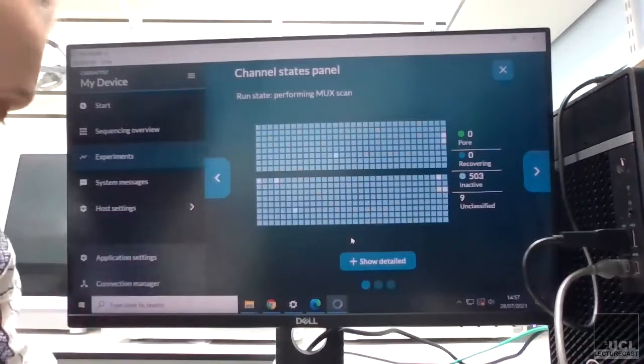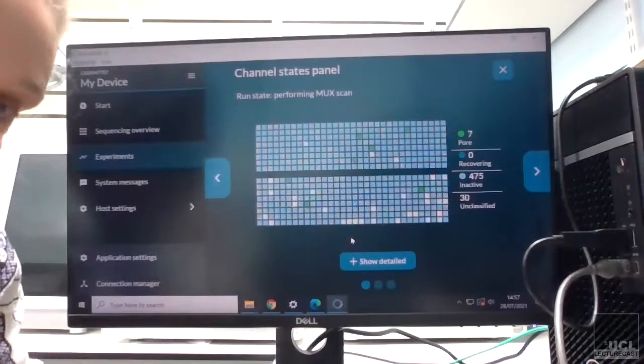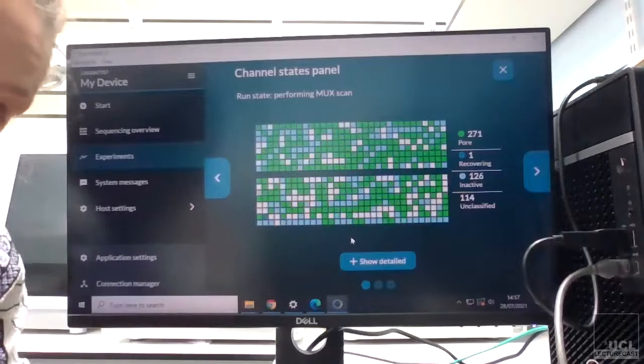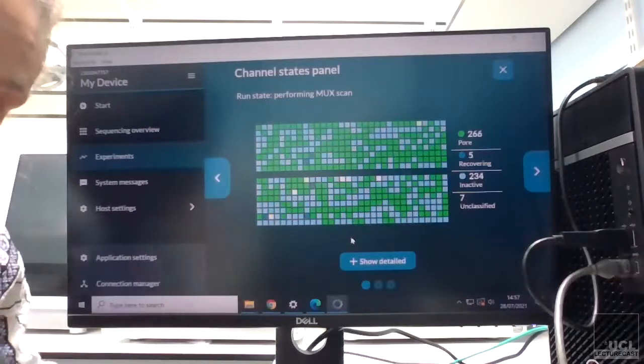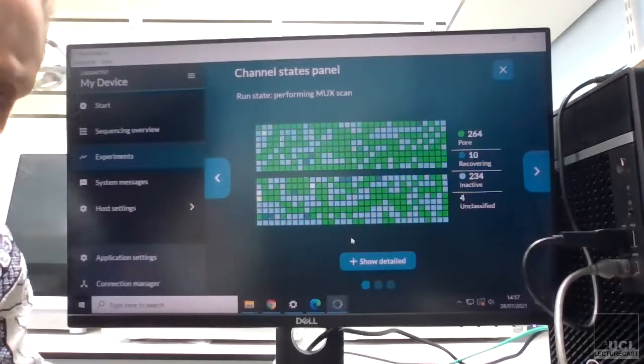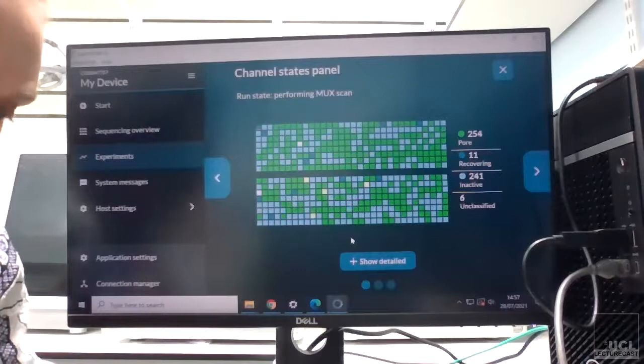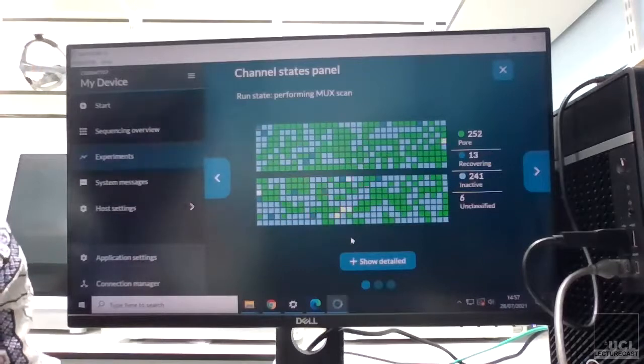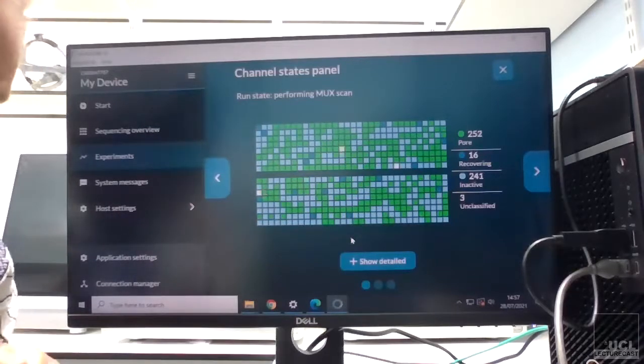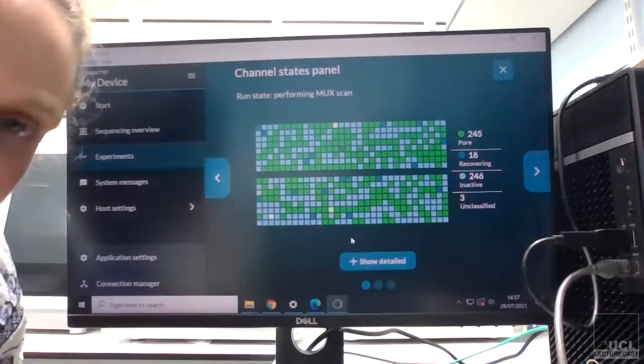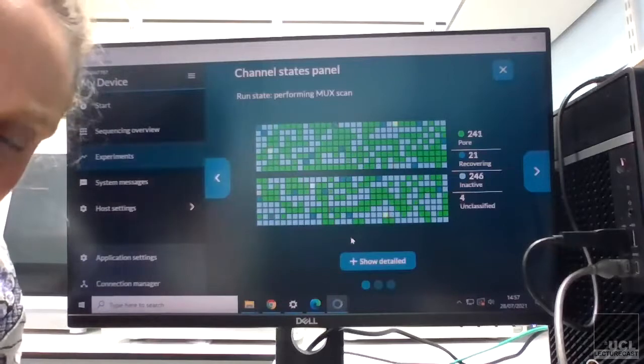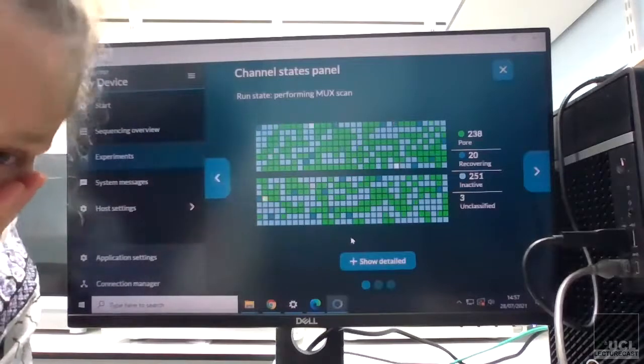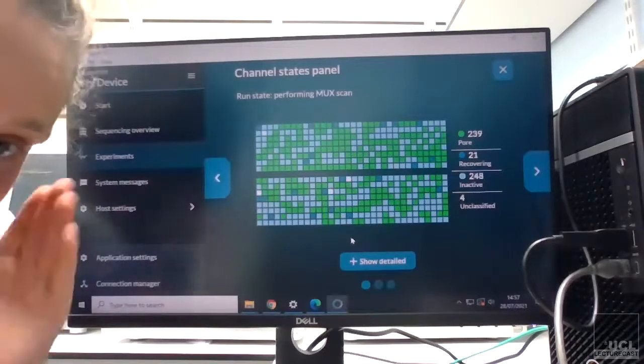So what Nanopore said to me when I did it and got below 800 is that you should take it out, switch everything off and turn it back on again, and then retest the flow cell. And I think there was also something else that they requested that you do, which was just check that there was no bubble in front of the sensor.